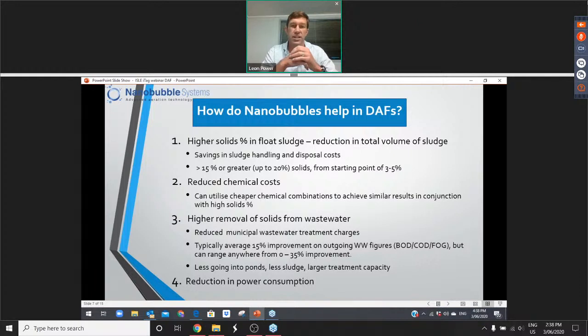Pretty much every installation they've had in the States, they've never had a solids percentage of sludge less than 15%, whether they're starting at really low percentages, 3 or 5% or 10%. That's sort of the key figure you get, and that's the primary reason most of the sales have happened. The next strongest reason is people have played around with the combinations of chemicals they're using.